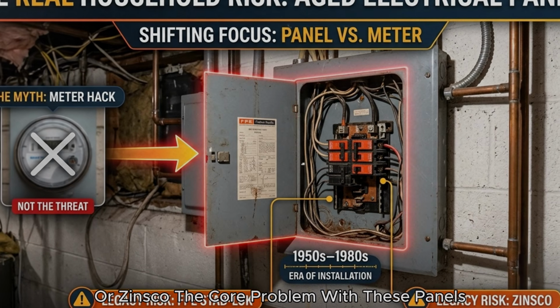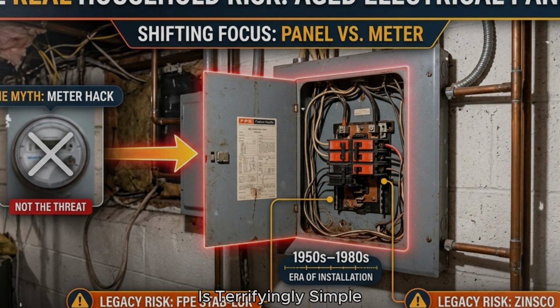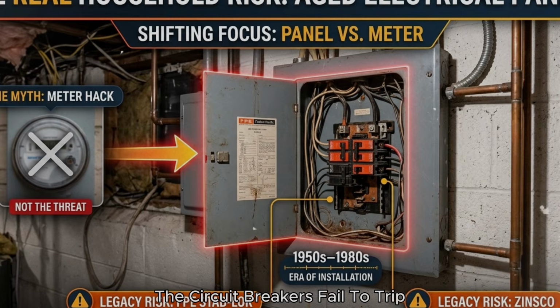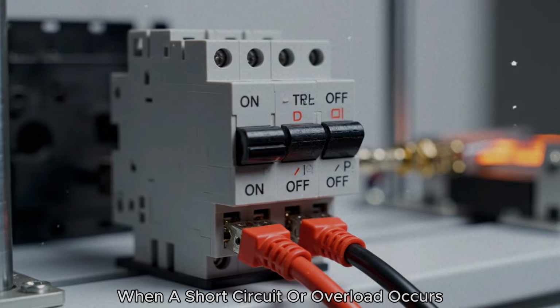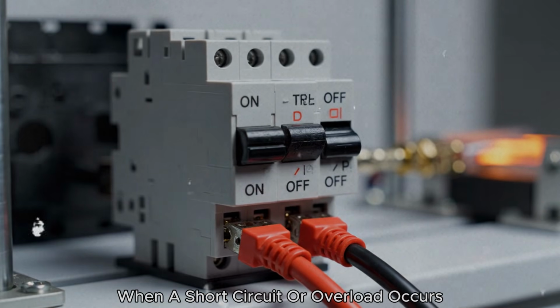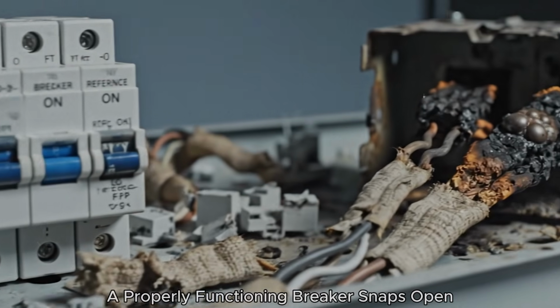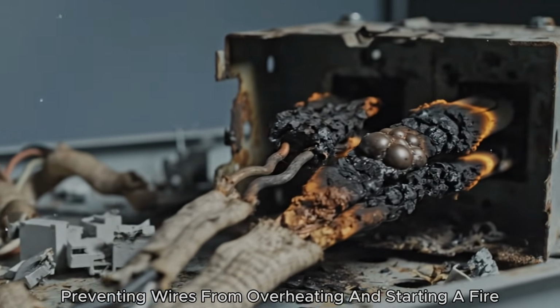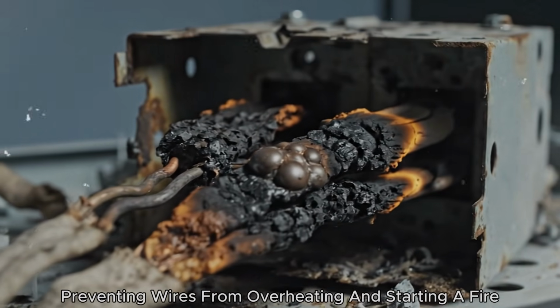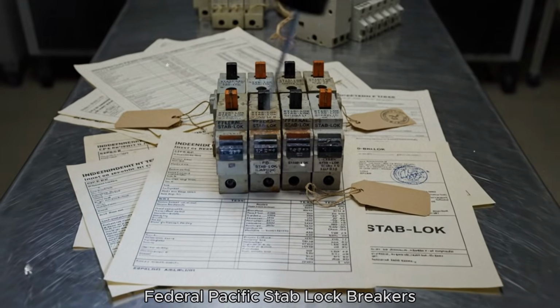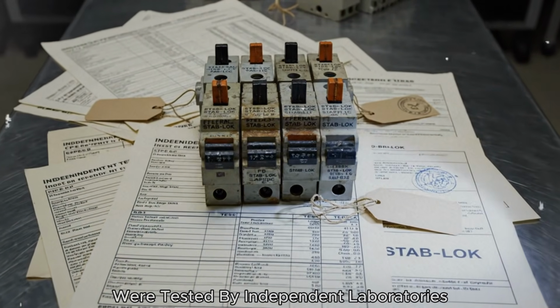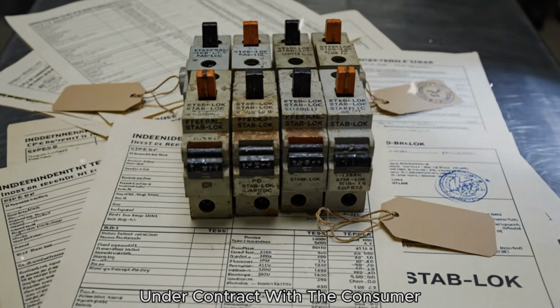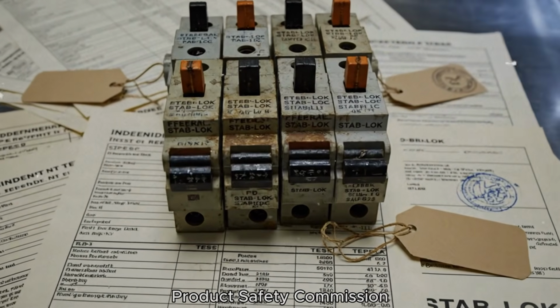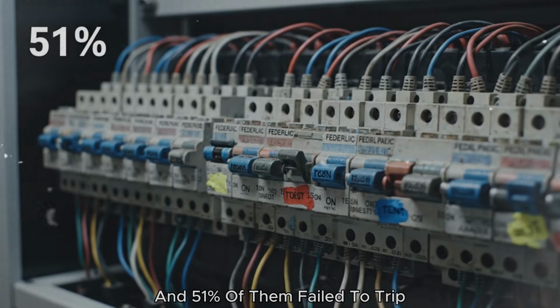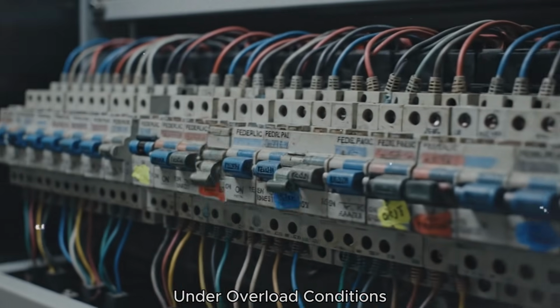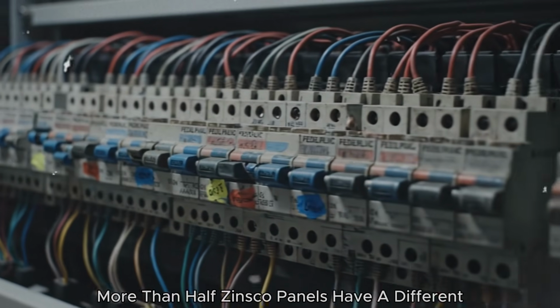The core problem with these panels is terrifyingly simple. The circuit breakers fail to trip. When a short circuit or overload occurs, a properly functioning breaker snaps open and cuts the power, preventing wires from overheating and starting a fire. Federal Pacific Stab-Lok breakers were tested by independent laboratories under contract with the Consumer Product Safety Commission, and 51% of them failed to trip under overload conditions, more than half.